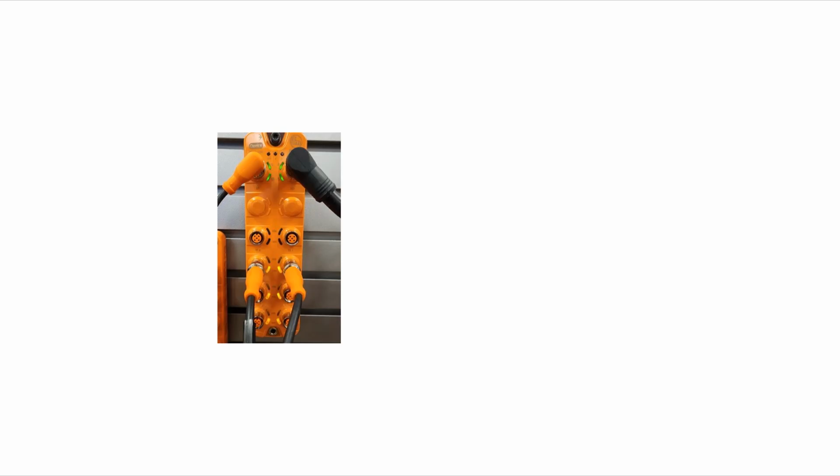The first thing we want to note at the beginning of the video here is that the acyclic enhanced mode has not always been a function of these AL2 hubs. It was not until the hardware revision BB or higher that this functionality has been included. So keep in mind the AL2605, 2205, they need to have on the right side of them HW for hardware revision BB or higher in order to use this mode.